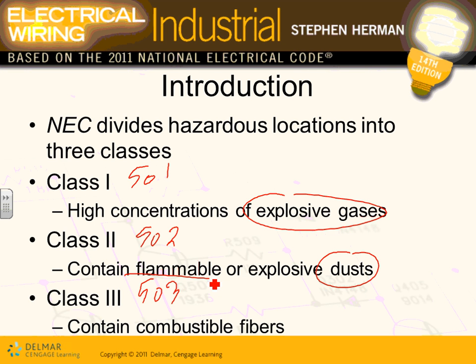So any places that have chemicals, there's a lot of chemicals, guys. If you have a chemical refiner that creates a dust, not a gas, not a vapor, and that cloud of dust can ignite and make an explosion, you're looking at a Class 2 location. Class 3 location is fibers. These are wood shops, paper mills. Wood shops can be classified as a fiber, Class 3 location. So you're talking about wheat refineries, wheat mills, wood shops, like I said, paper mills. All these have fibers that can be combustible. It can ignite and explode.